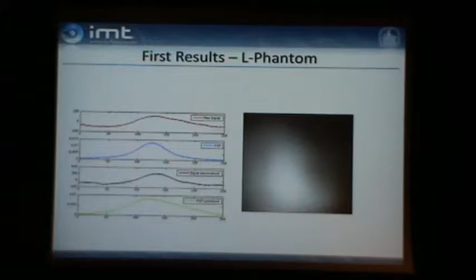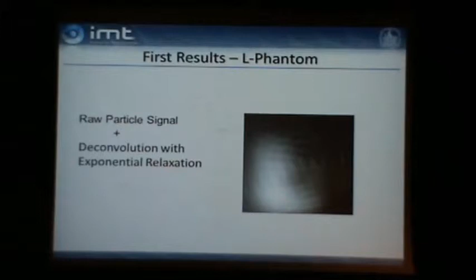The first is the relaxation. When the field-free line goes over the particles and then comes back, the particles remember that they have been polarized in this direction, and this is not the state in equilibrium. So we are not done with relaxation, and we have to reduce the errors from this by deconvolution. So this is without, and this is with exponential deconvolution of the relaxation. And then, of course, the point spread function from the Langevin function can be used for a second deconvolution, and this is then the result of the L.